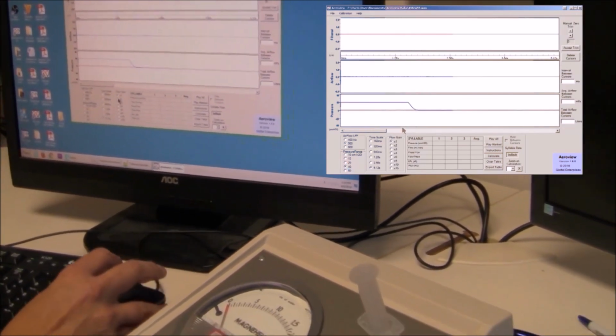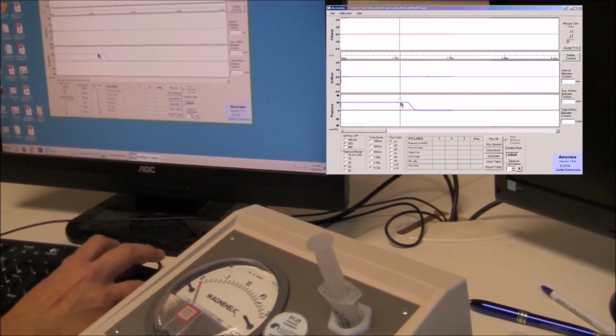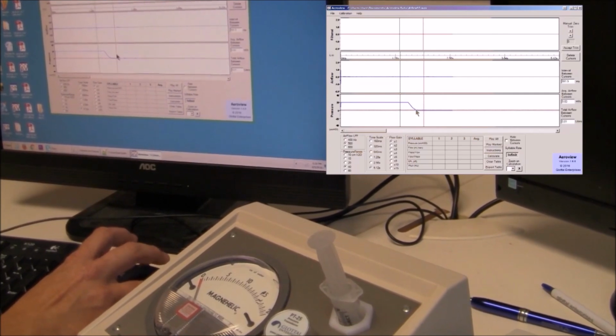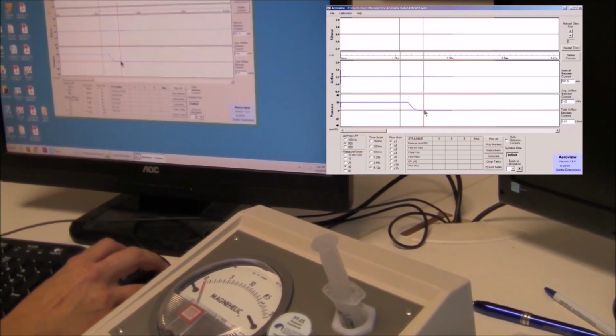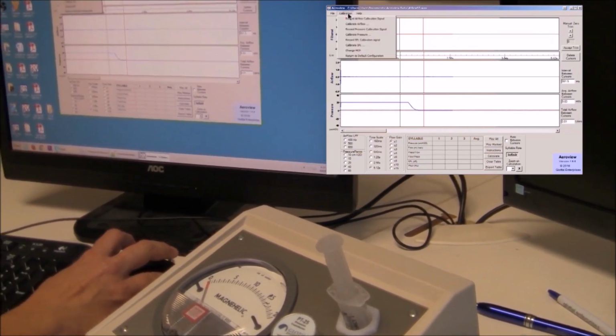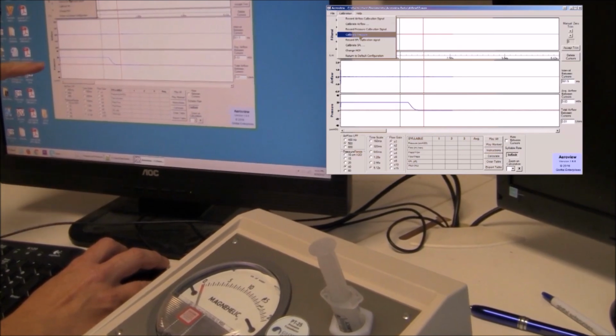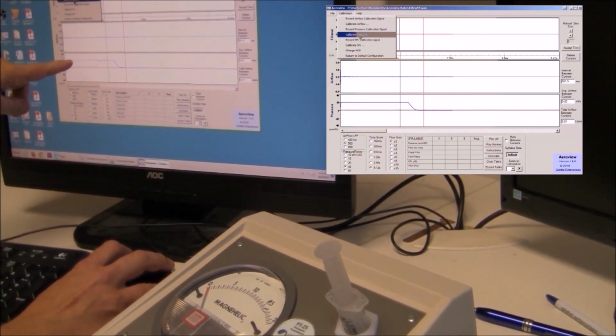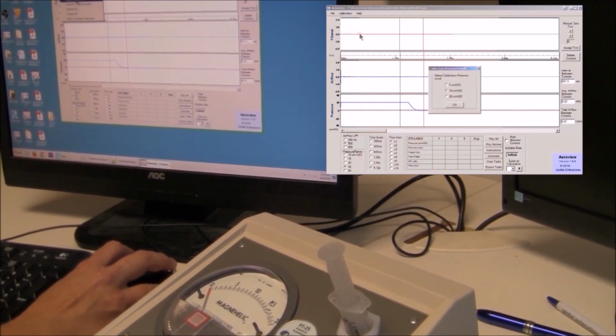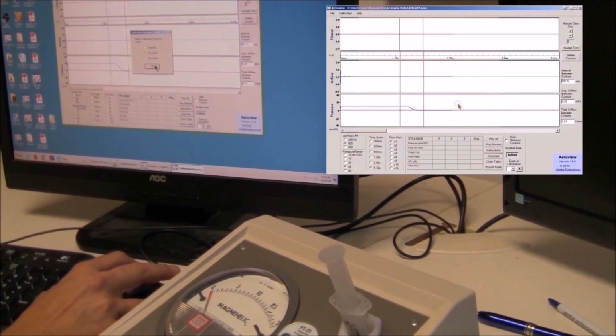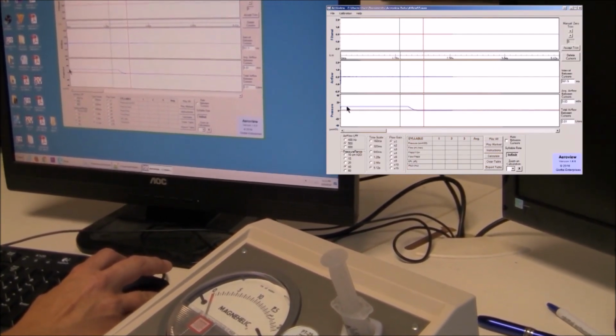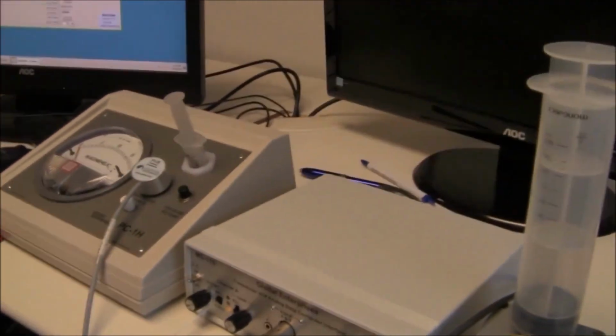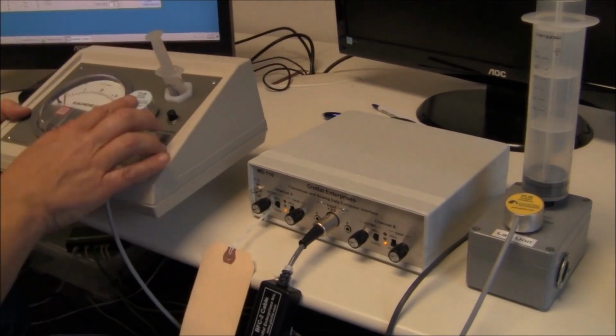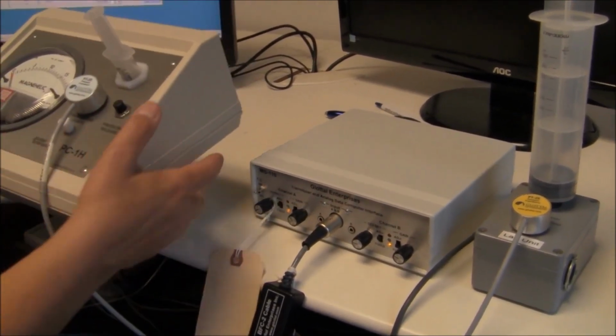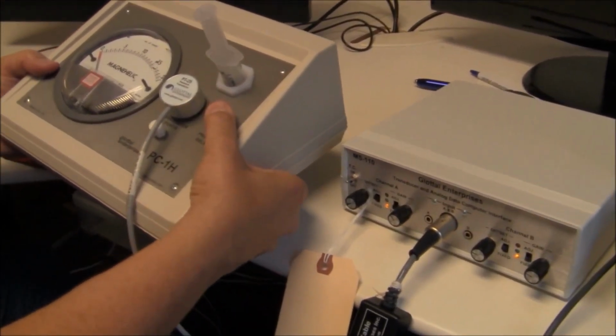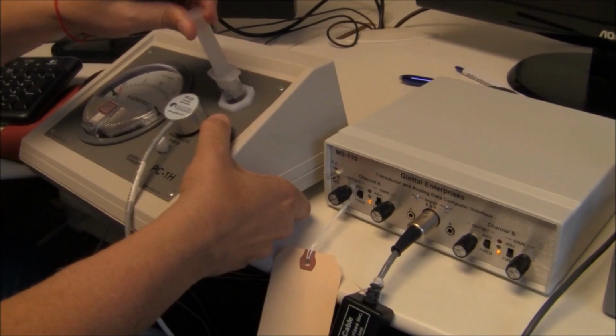So to make it a little more visible, that's too much. Okay, that looks good. So now we're going to click to the left, and we're going to click to the right. So you want to click on the two flat spaces, and then we are going to choose calibration and calibrate pressure. And you're going to see that this line will then line up with 10 centimeters of pressure. So you want to pick 10 centimeters, and now it's calibrated. See, it's at 10. Okay, so now we've calibrated the pressure calibrator, and I just want to remind you to always have the pressure release button pressed when you're pulling up on the syringe.